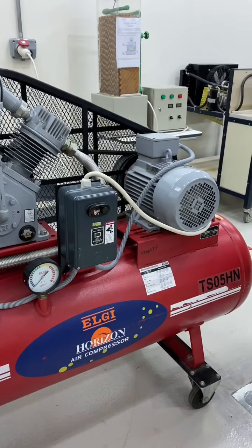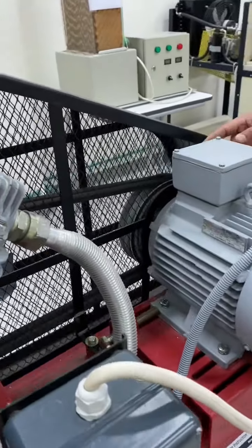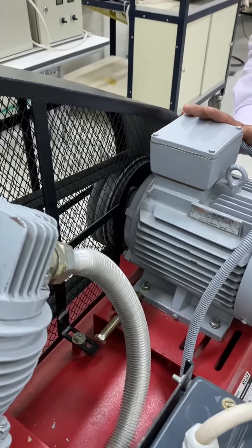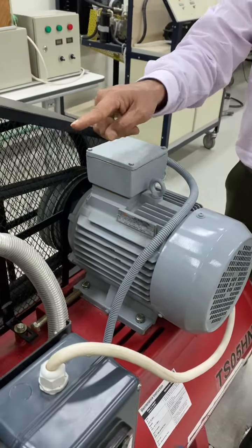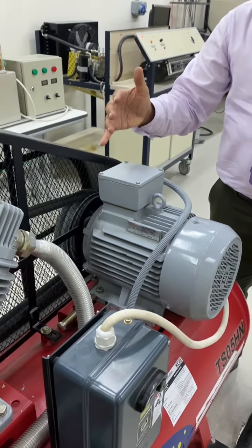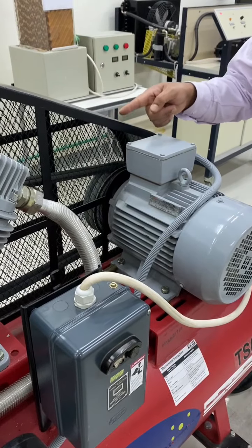And then you can see this is the driver pulley here, and then there is a driven pulley to run the reciprocating compressor. You can see the driven pulley on this side. This driven pulley is bigger than the driver pulley. Why? Because the speed is reduced. Here the motor speed is high, and that speed is not required to run the compressor. That is why the pulley is bigger. A bigger pulley means speed reduction, and the driver pulley and driven pulley are connected by means of a belt.